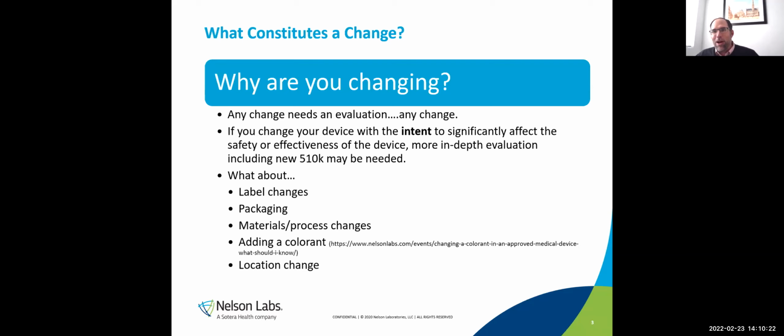The cytotox came back positive on the device made in the new facility. So we hurried up and ran a device that was the last device made in the old facility, and we ran them side by side. And the old facility device passed, and the new facility device failed again. So now we're like, okay, we have a confirmation that something happened in the move. So the next step was we did some chemistry to evaluate what could have changed, what could be the difference between the old and new device.